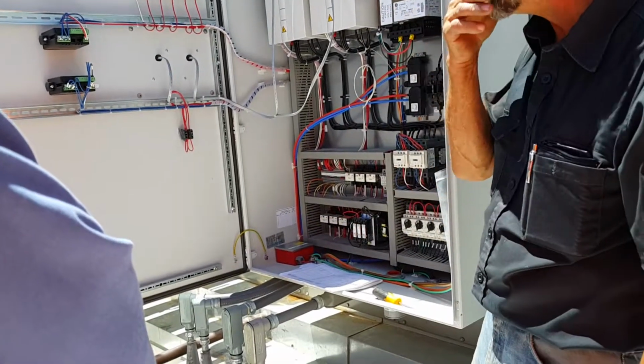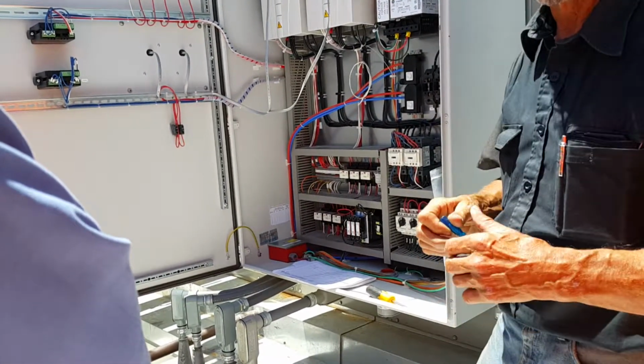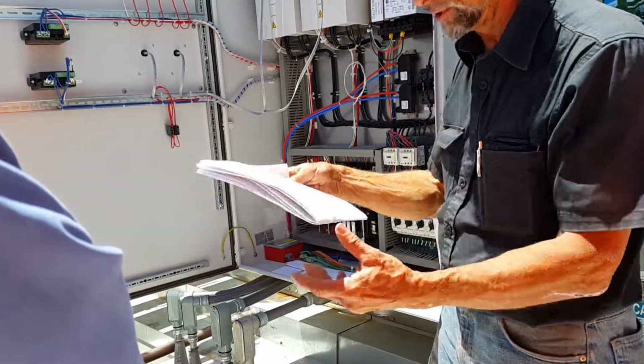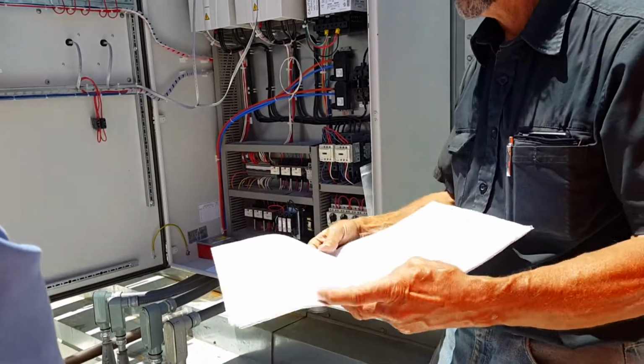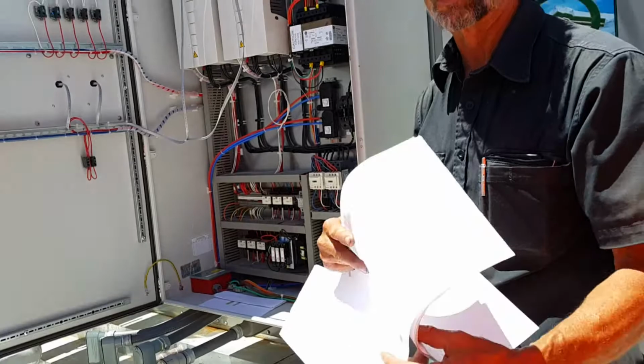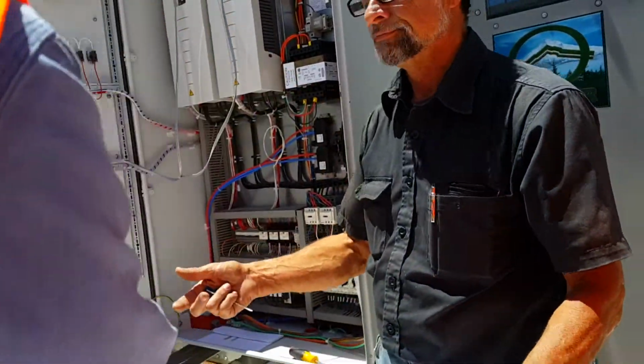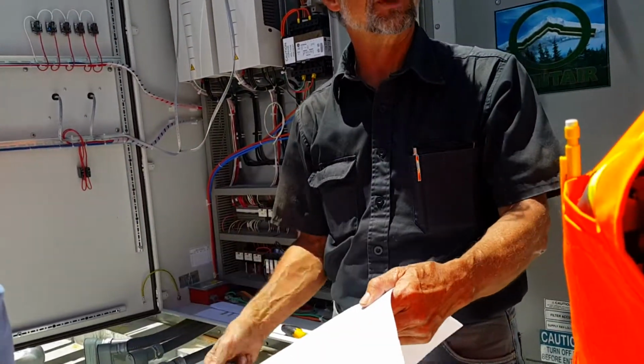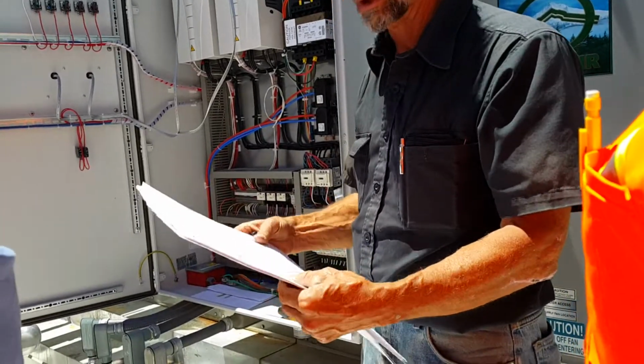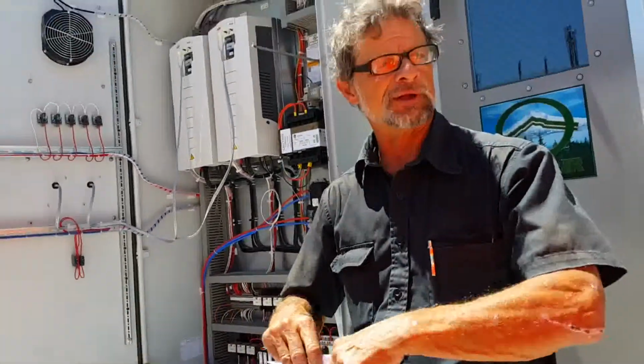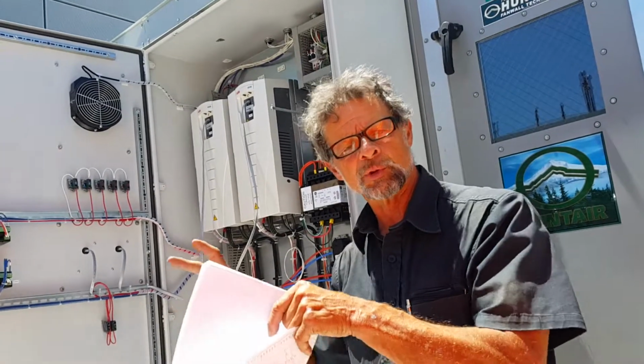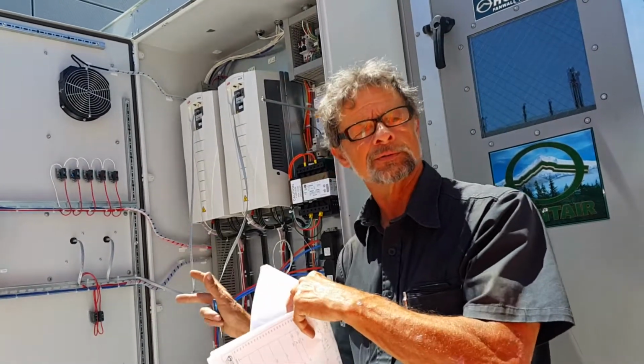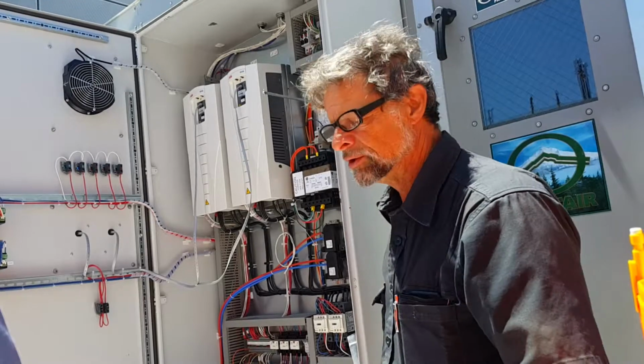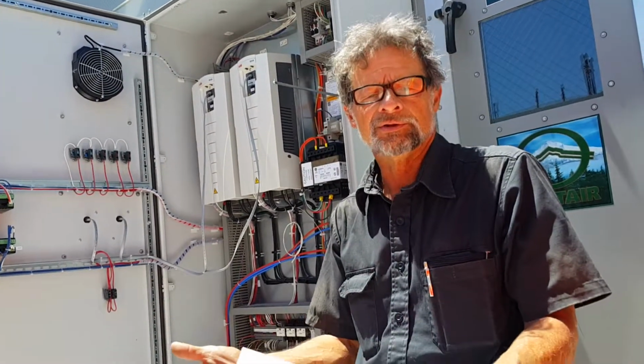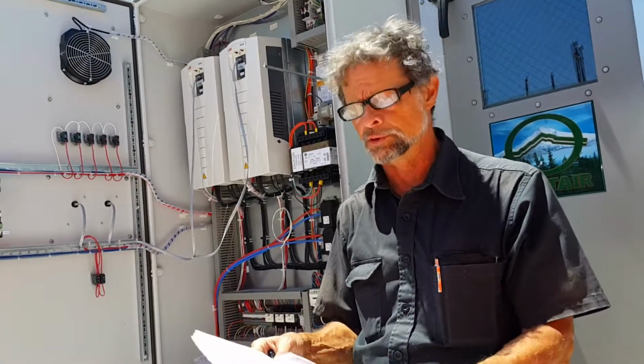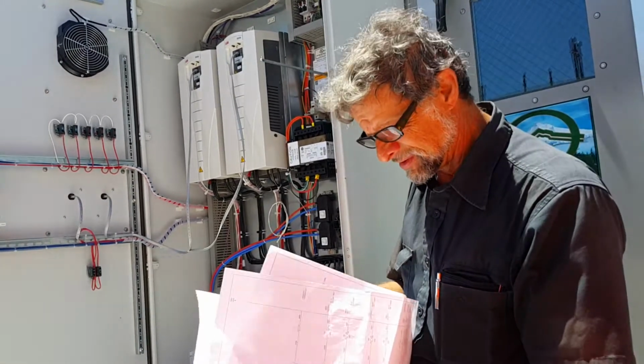You can pick that up, and what he's supposed to do is take the information off of the unit that says 4 to 20 milliamps equals 0 to 40,000 CFM or whatever it is. Now that doesn't mean you'll get 40,000 or you'll ever see the 40,000. That's just the way it's programmed for that cone and that fan. So your actual, you might only be designed for 20,000, but he'll scale it. It should be on here.